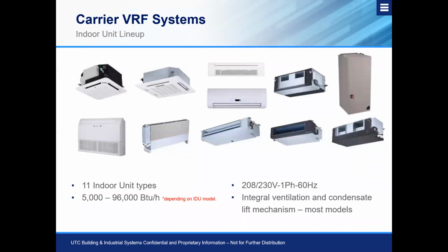Now, as far as the indoor units go, we have a wide array on the Carrier VRF system. So we have our cassette style units. If you look from left to right, the first unit that we see on there is going to be our 2x2 cassette. And the unit to the right of that is going to be our 3x3 cassette. Both of these units were developed obviously for ceiling grids to be able to recess up and sit flush in there to blend in with the space. They can also be used in industrial applications by the use of all thread and unistrut to be able to suspend them centrally in the room and to give that nice exposed look.